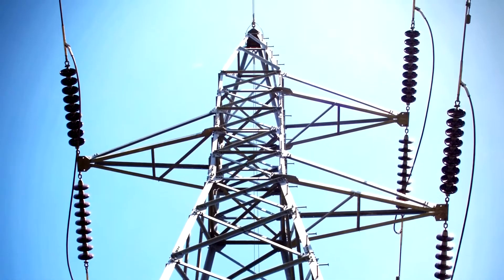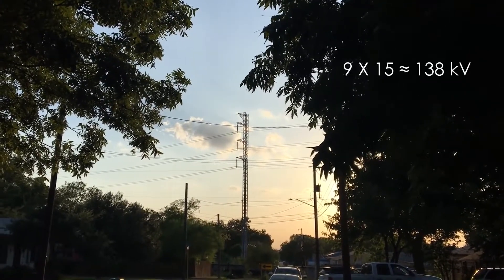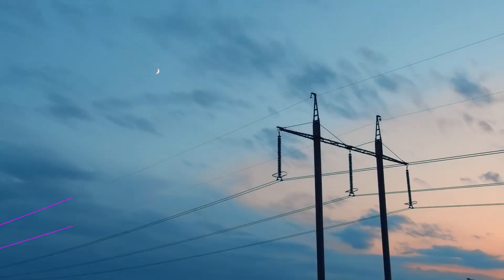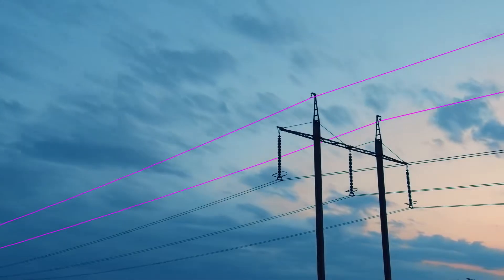These discs are somewhat standardized, so this is an easy way to get a rough guess of a transmission line's voltage — just multiply the number of discs by 15. For example, this line near my house has 9 discs on each insulator, and I know it's a 138 kilovolt line. You'll also often see smaller conductors running along the top of transmission lines. These static or shield wires aren't carrying any current — they're there to protect the main conductors against lightning strikes.